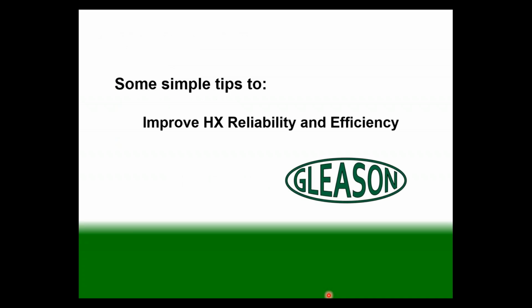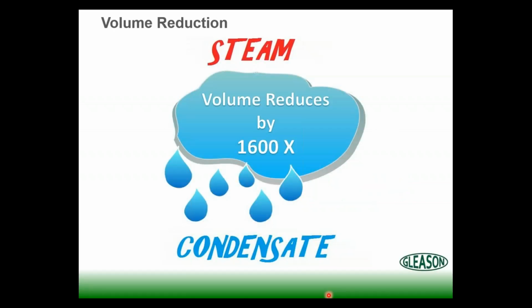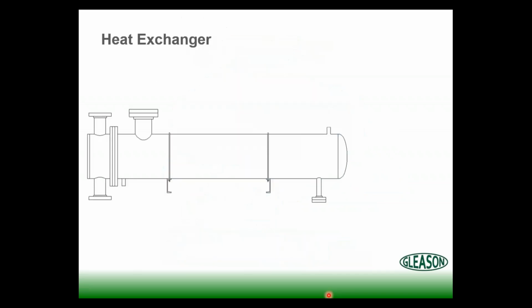Some simple tips to improve heat exchanger reliability, some of our bullet points. First off, keep in mind when we're talking about heat exchangers, when steam condenses at atmospheric pressure, its volume reduces by about 1,600 times. So let's say we have an application for a heat exchanger. One of the first questions I ask folks when we go in to do an audit or a review of a system is, do you have any tube bundles that are failing prematurely? Many times they're like, yeah, man, this has been killing us. And we'll walk back to it.